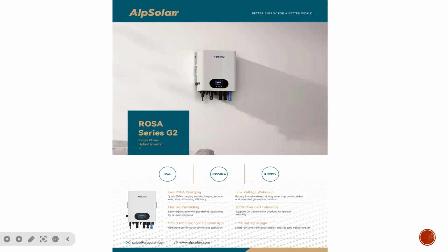Many people design an inverter that does not have enough charging current with a lot of batteries, and you're asking yourself, for how many years is this inverter going to charge this battery? And then let's even say from the PV. It means all through the day the inverter is busy trying to charge the battery, and it's not even supplying power to the load in the house because the charging current is quite small. So this guy having a 230 amps charging current gives you the opportunity to oversize your battery bank, and you are rest assured that it's charging it. It has both charging and discharging current of 230 amps.